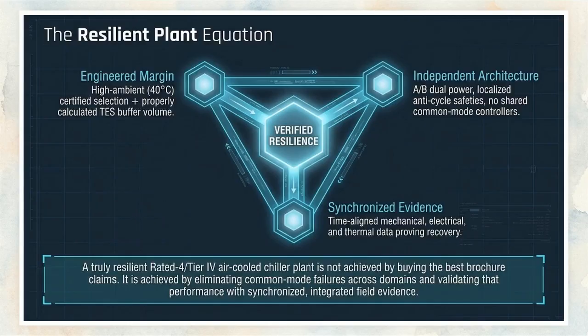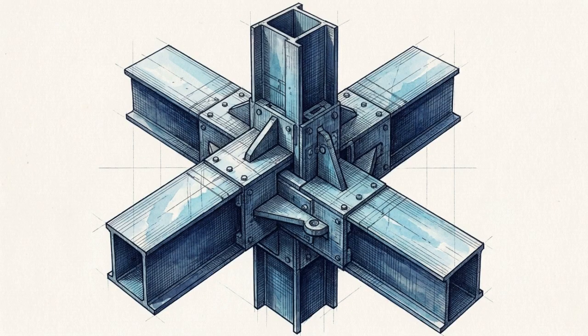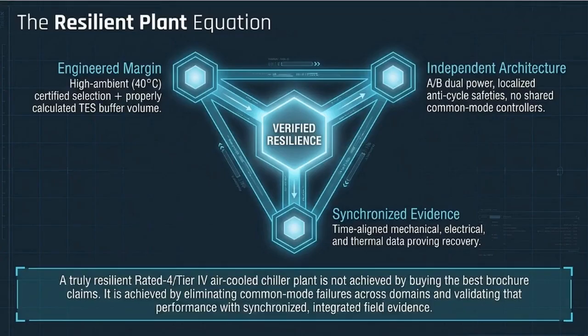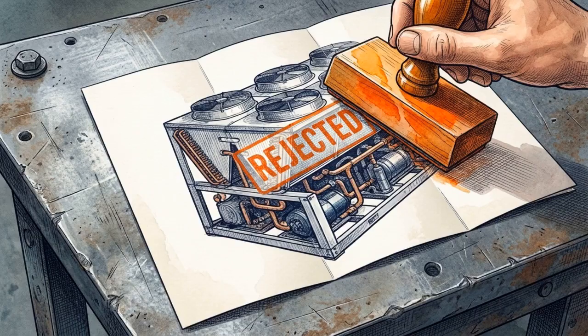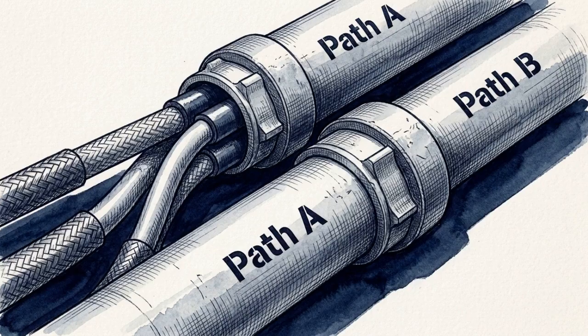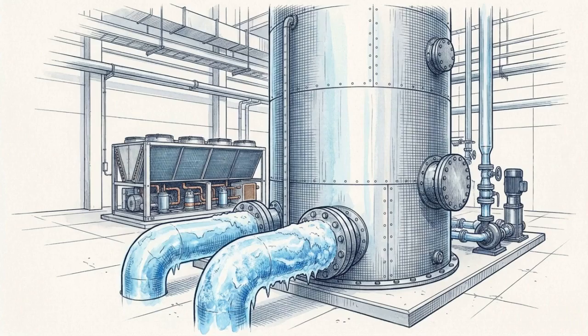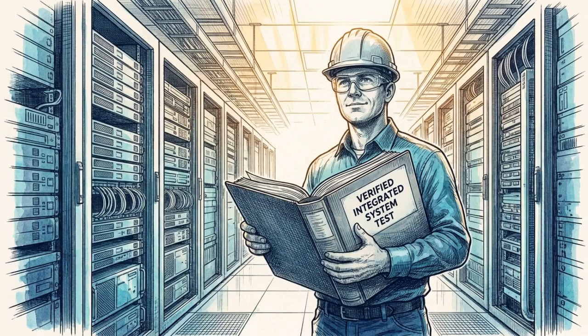Looking back at the resilient plant equation diagram maps out exactly what makes an air-cooled data center truly resilient. Surviving the thermal gap requires three non-negotiable pillars working together: the engineered margin of the thermal buffer tank, a fiercely independent power architecture, and synchronized telemetry providing actual evidence of heat transfer. A Tier 4 air-cooled chiller plant is not achieved by purchasing equipment based on brochure claims. It is engineered by systematically eliminating common-mode electrical failures, bridging the physical thermodynamic gap with calculated thermal storage, and proving execution through unrelenting, time-aligned empirical evidence.